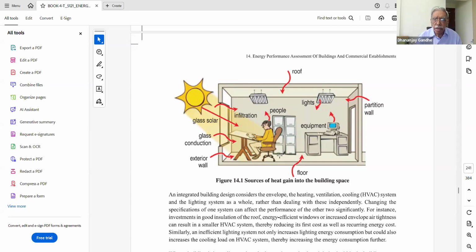So it heats the inside atmosphere. And if the room is to be air conditioned, we have to first calculate what are the heating loads, what are the sources by which the internal atmosphere gets heated, what causes the heating. So one is the solar radiation coming through the walls, second is infiltration air, third is through the glass, where a certain amount of heat conducts inside, so it is through conduction. Also, through the external wall some amount of heat goes in, because although brick wall is an insulation, it's not 100% insulation. So some amount of it can go inside.